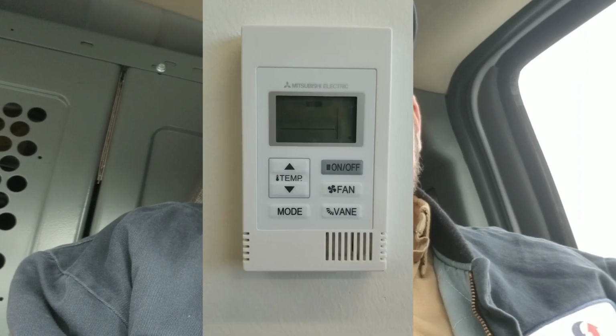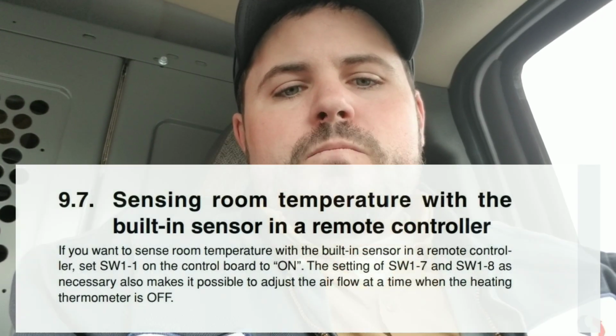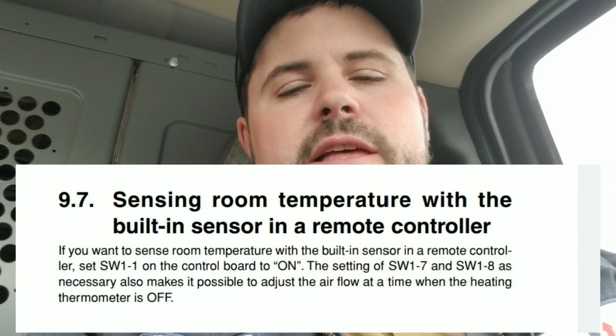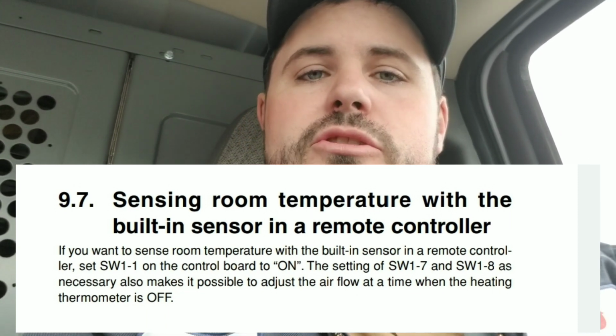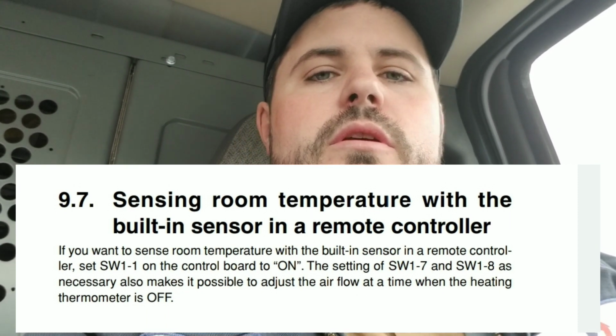Okay, so the second error, stat was flashing a 5101, which is a return error sensor fault. This is the error you'd get if the return air sensor went bad. This was a ducted ceiling concealed style unit. From the factory, they control off the return air sensor. If you want to add a thermostat, you have to flip switch 1-1 to the on position, and then it will control off the thermostat. You can actually use a thermostat and control off the return air. You can do that as well.